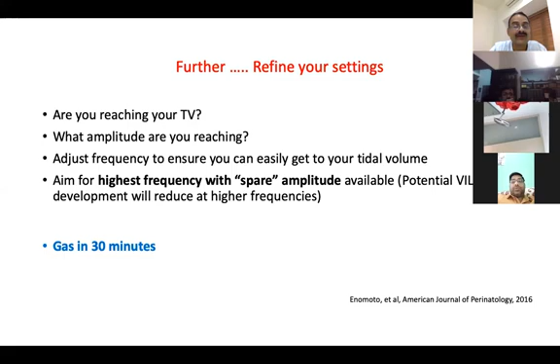Further adjustments are actually based on when you wean. Suppose you have reached the target, and then slowly CO2 is slightly building up. You may need to increase. You are not using a correct frequency, because nobody told us babies don't read textbook, and they don't know that they need to have 2 or 2.5, whatever you have set. So if they are not reaching the target, you adjust your frequency. Usually you never need to go up more than 2.5, 2.6.